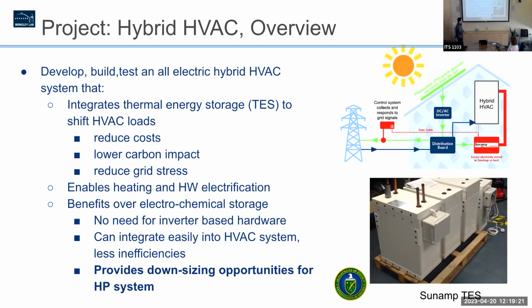One really great thing about thermal energy storage is the ability to downsize your system. A lot of heat pump systems, a lot of HVAC systems currently are sized to kind of peak load, so you just oversize the system. A lot of the year, you're not actually needing that much capacity. With a thermal energy storage system, you could take that peak value and maybe have 30% of the capacity coming from thermal energy storage, 70% coming from the air water heat pump, and that way you're not having to oversize your system like we've traditionally had to do.